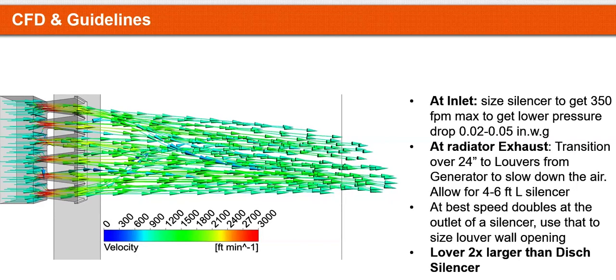Those are good points. So as we continue with this, at least the minimum design guidelines I want to give you, at least for the inlet, is that opening. You have a lot more play on the opening to bring air into that generator, electrical mechanical room. So as long as you size that silencer and the louver to have a face velocity to not exceed 350 feet per minute, you can keep your pressure drop really low.